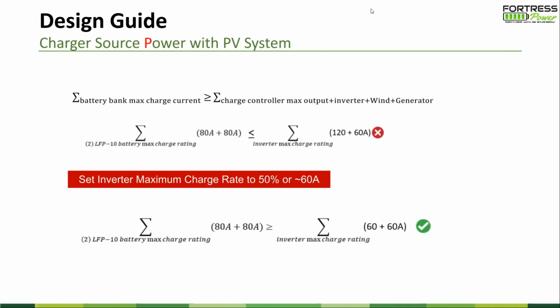Yeah, what do we do? Most of the inverters and charge controllers are highly configurable, so you can configure the charge rate to the battery spec. You can derate the charge rate from the inverter side, and also from the charge controller MPPT side. So just try to tweak it under 160 and you'll be safe. In this case, I tweak everything to 60 amps, so if both of them charge the battery at the same time, the maximum will be 120 amps. That will be pretty safe for the charger situation when you charge the batteries.